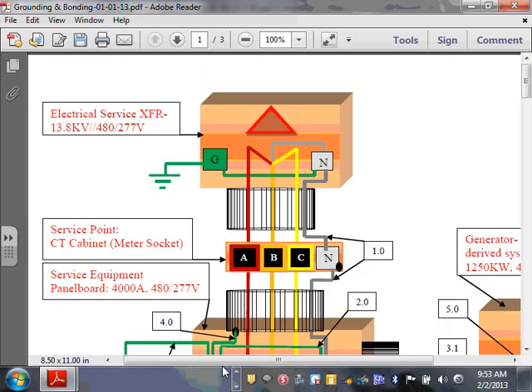Do you guys know why? A couple of reasons. You know how many times we go up 25% before we reach the service? That 25% is the safety factor. So just imagine, every conductor, every panel that you do, we throw an extra 25% on it. And because they don't make standard transformers, if you end up with a transformer that's not a standard size, what do you do? You go up again, right? So imagine how many ups and ups we go by the time you reach the service. Your demand load actually is probably 50% of what you size for. So they are completely right, and they have the numbers to prove it too. We don't have the numbers. I don't collect numbers about hospitals nationwide, so I can't argue with people.